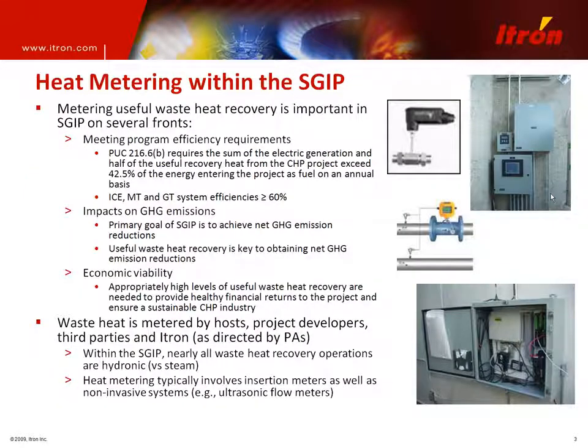So let's talk a little bit about heat metering within the program. Really, there's three major areas where there's value in heat recovery and in measuring heat. First off, almost all projects have to meet some sort of efficiency requirement. That's true in California as well as elsewhere in the country. In California, there's a public utility code requirement that the sum of the electric generation and half of the useful recovered heat has to exceed a certain percentage of the energy entering the project on an annual basis. In addition, CHP systems have to exceed 60% system efficiency.